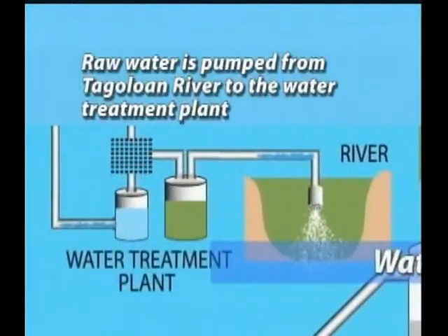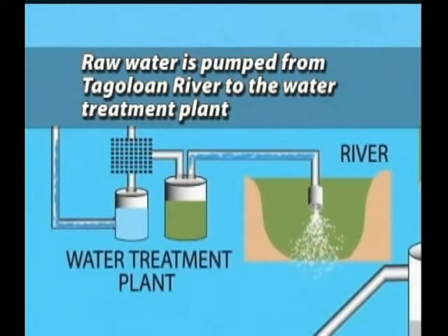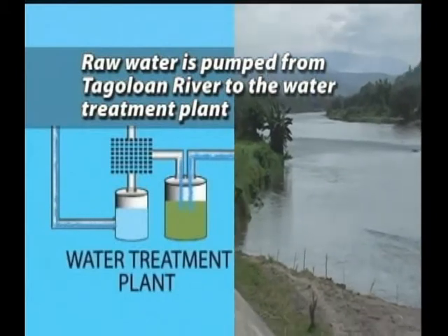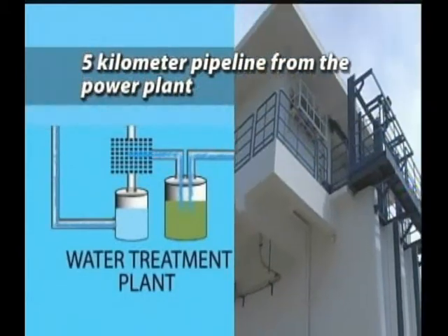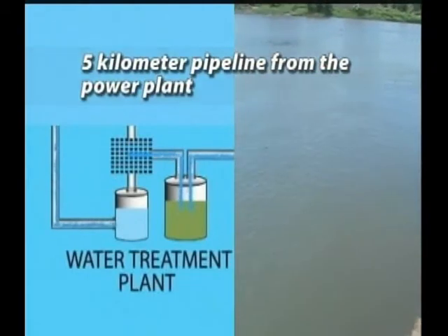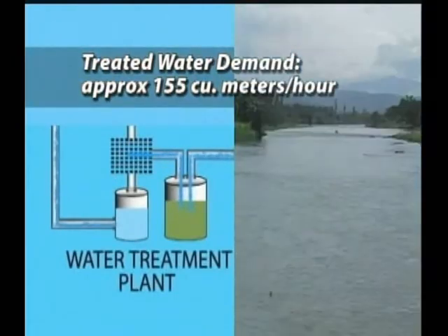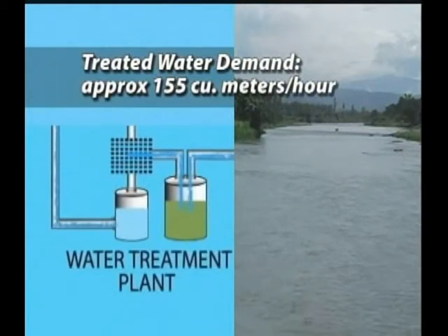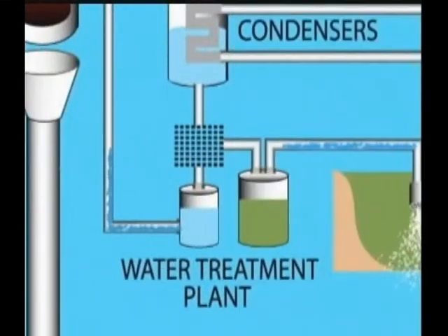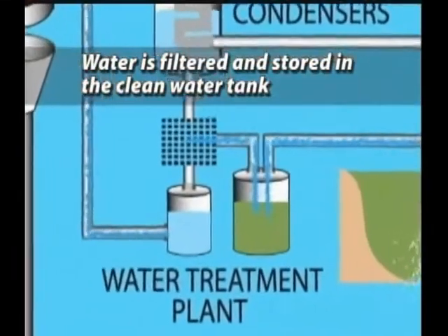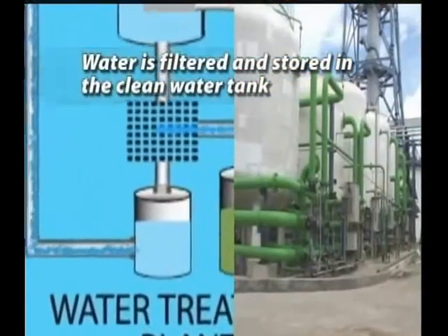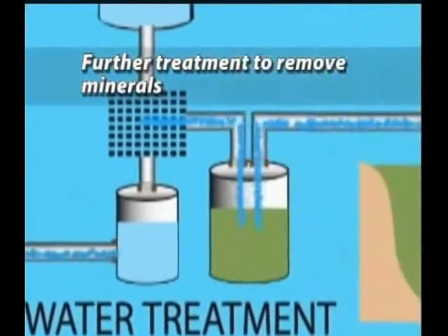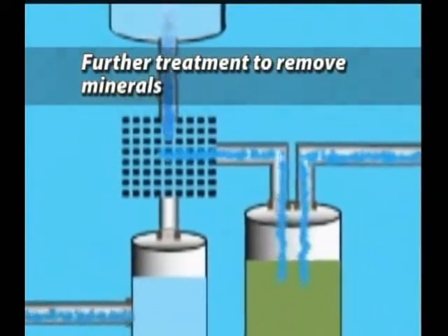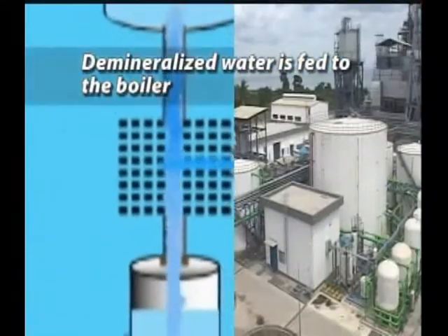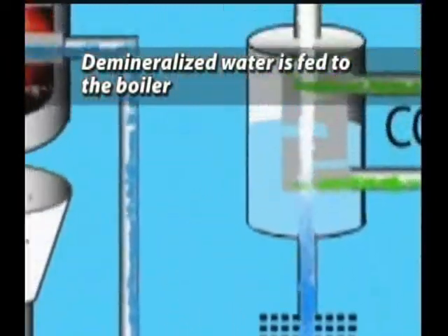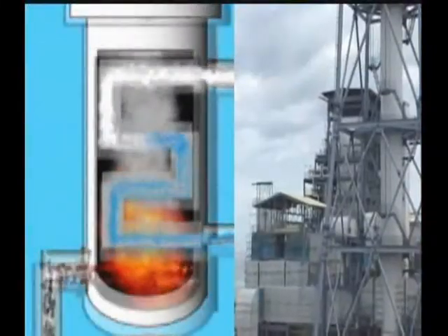Water. Raw water is pumped via an underground pipeline from the Tagoloan River to the water treatment plant located at the power plant, a distance of about 5 kilometers. Treated water demand for the plant is approximately 155 cubic meters per hour. At the water treatment plant, the water is filtered and stored in a clean water storage tank. This clean water is further treated such that minerals are removed. The demineralized water is then fed to the boiler as boiler feed water for steam generation.